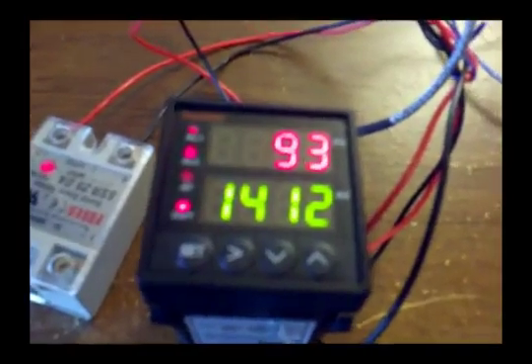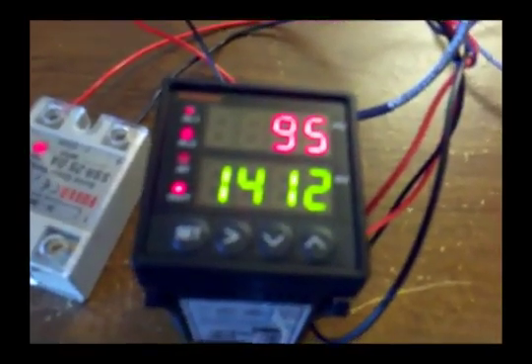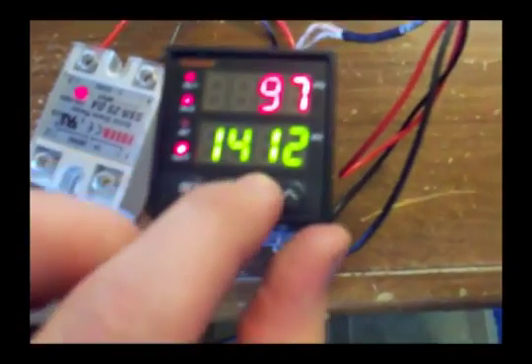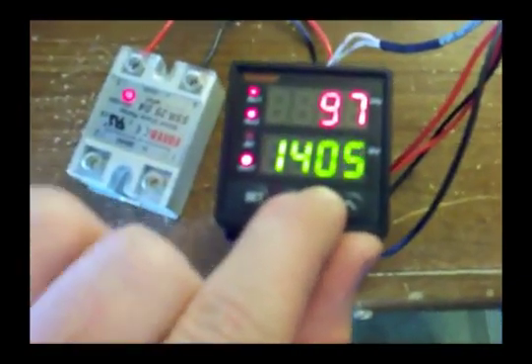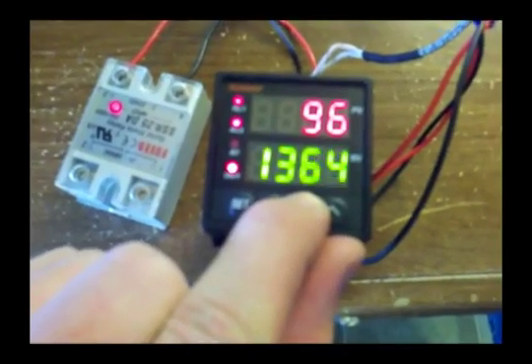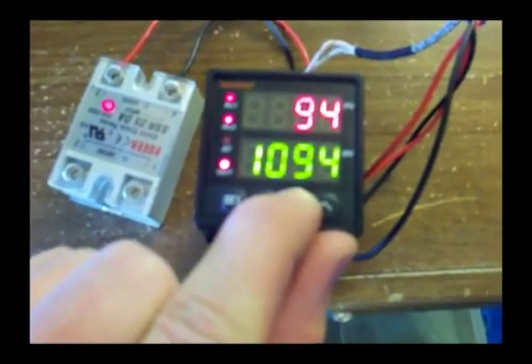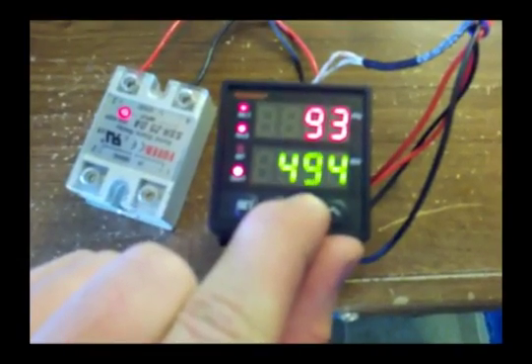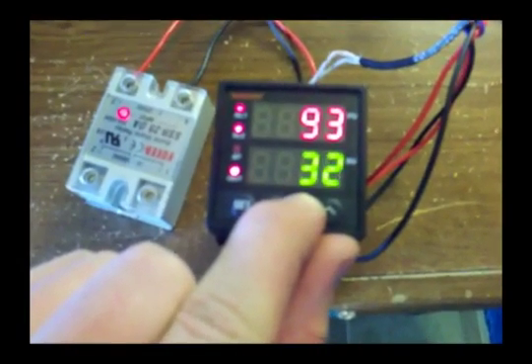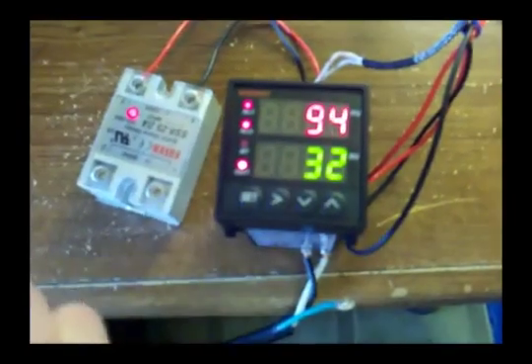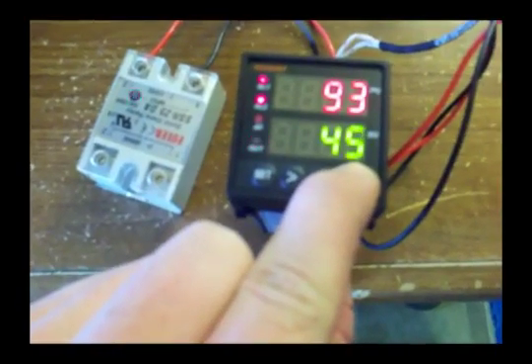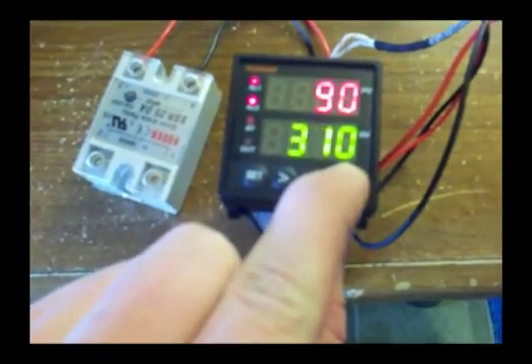The temperature range that I have it set to right now is 0 Celsius to 2300 Celsius. So if I press the down button in the Fahrenheit mode, guess where it's going to stop? It's not going to stop at 0, it's going to stop at 32 because that is 0 in Celsius. And I'm not even going to remove my finger. There, it stopped at 32. If I press the up button, it's going to stop at the Fahrenheit equivalent of 2300 degrees Celsius.